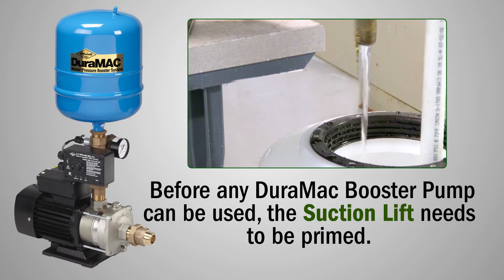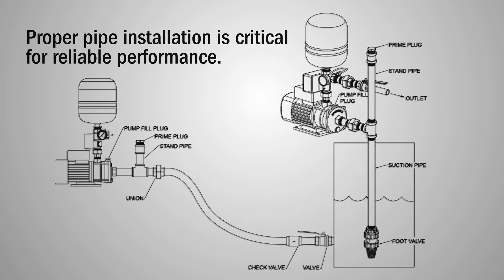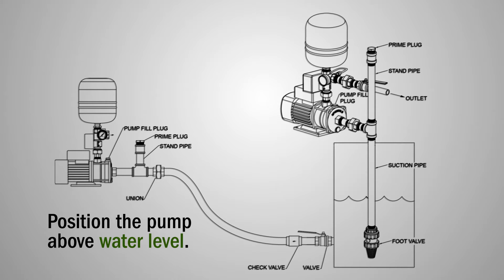Before any DuraMac booster pump can be used, the suction lift needs to be primed. But before you get started, you need to make sure the pipe is properly installed. Start by positioning the pump above water level and placing the suction pipe on a continuous slope with a foot valve installed on the end.